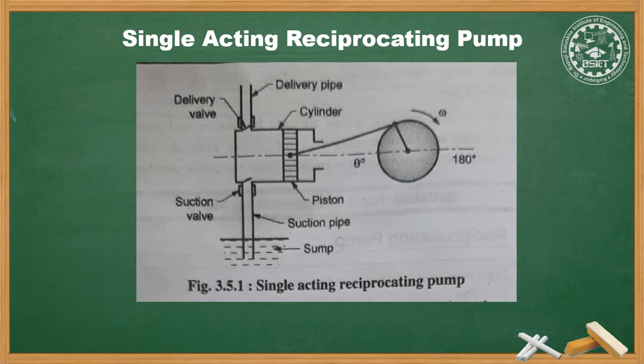In the suction stroke, the crank rotates from 0 to 180 degrees. The piston moves backward, creating a partial vacuum in the cylinder. Due to this, the suction valve opens and liquid from the sump is sucked into the cylinder through the suction pipe. In the delivery stroke, the crank rotates from 180 to 360 degrees. The piston moves forward, creating high pressure, and the plunger pushes the liquid out through the discharge valve while the suction valve is closed.